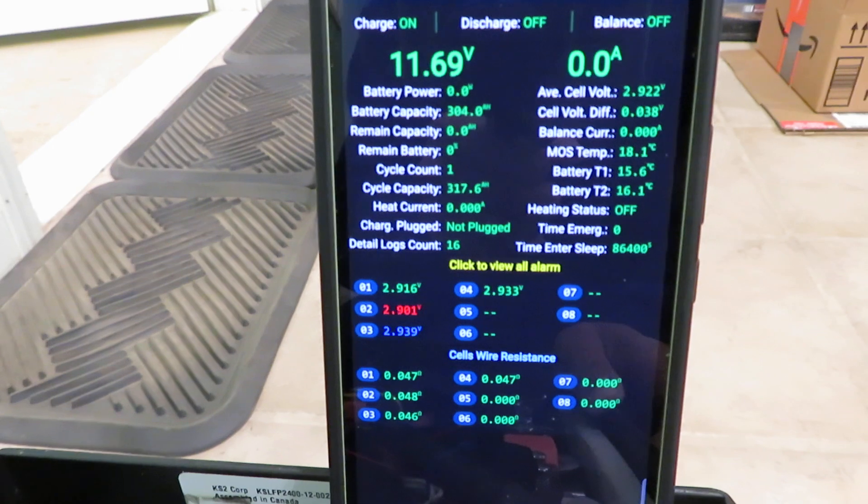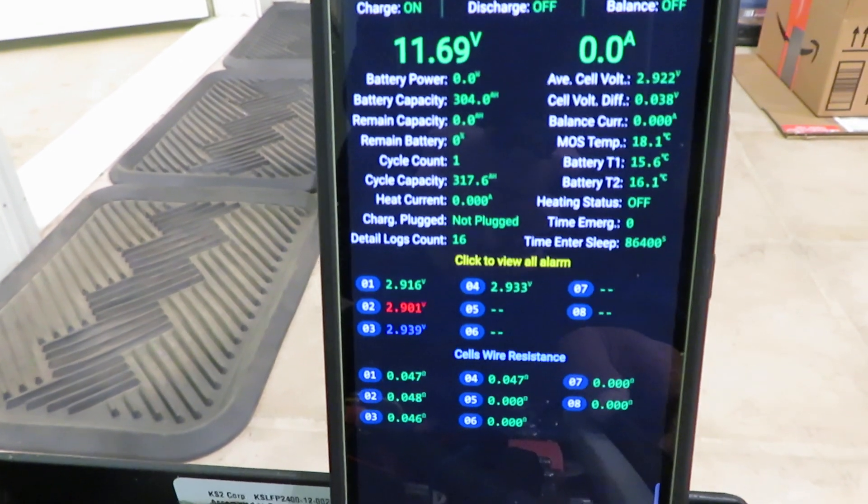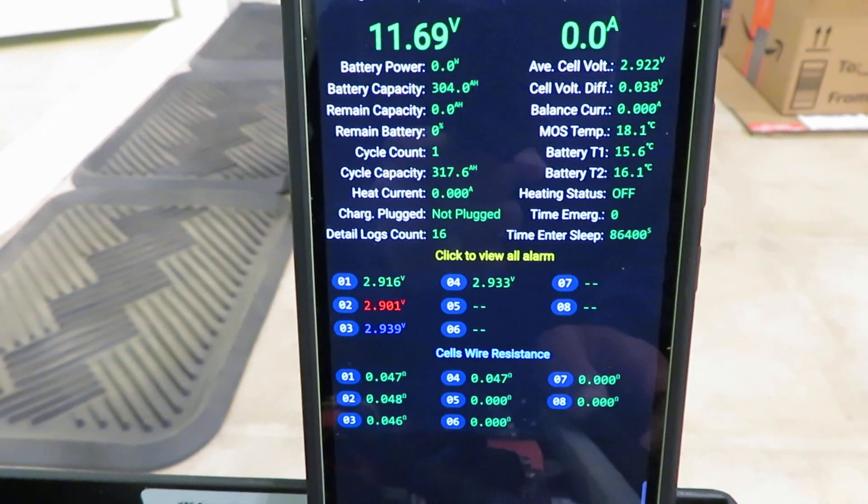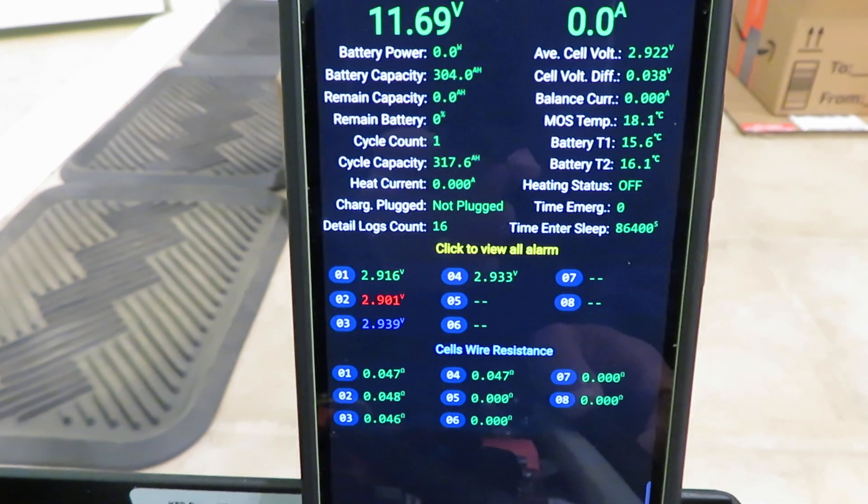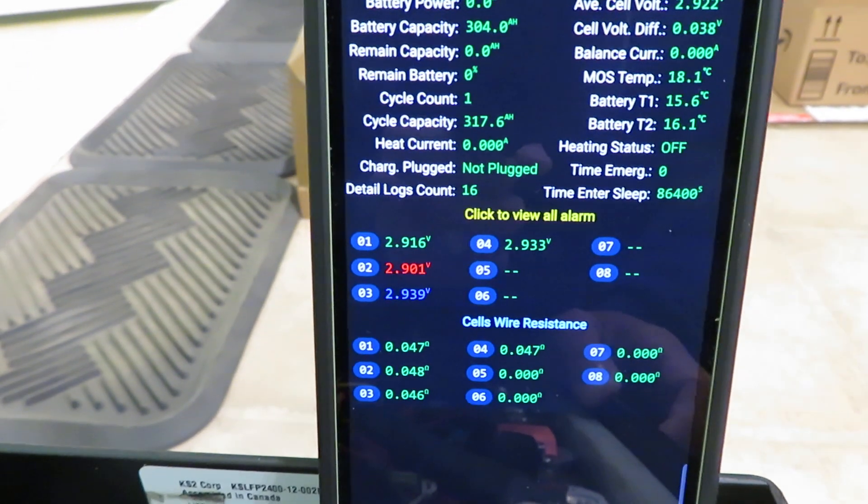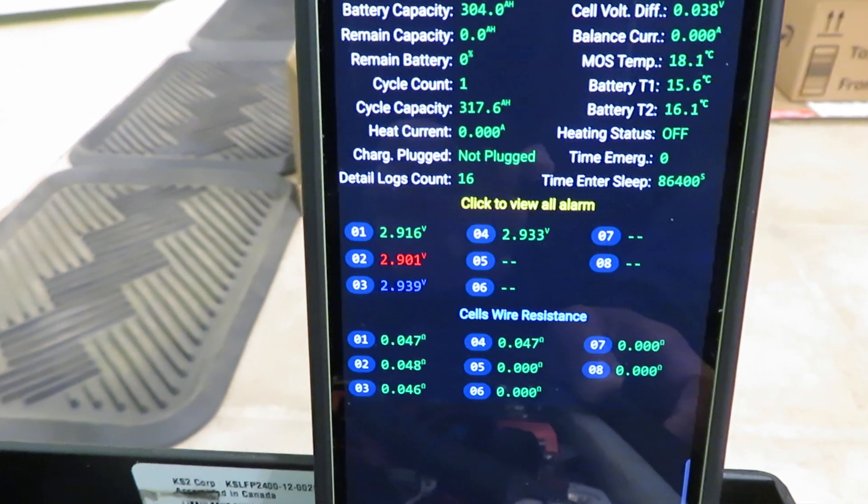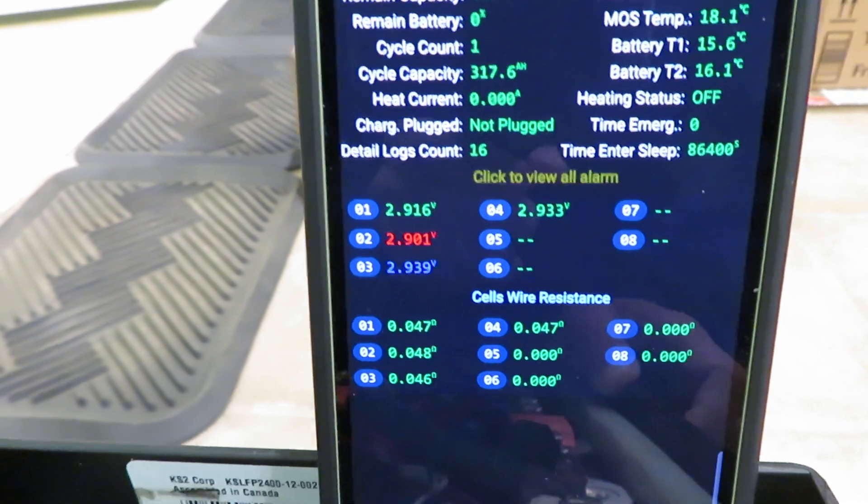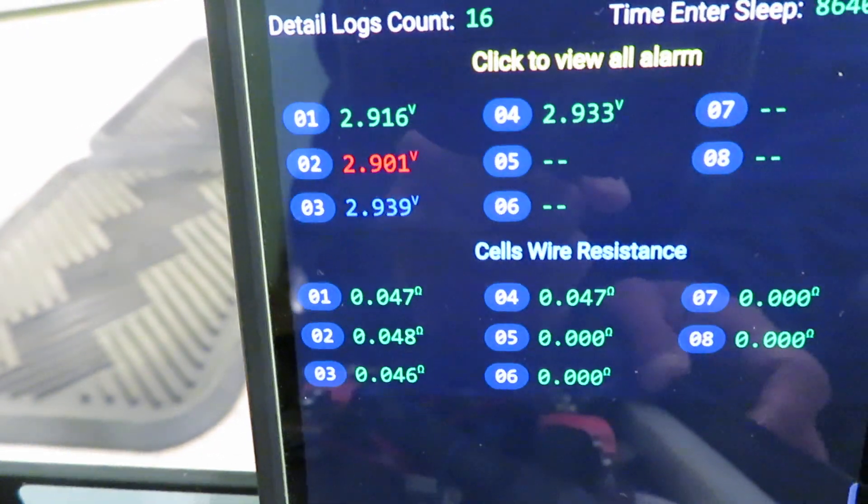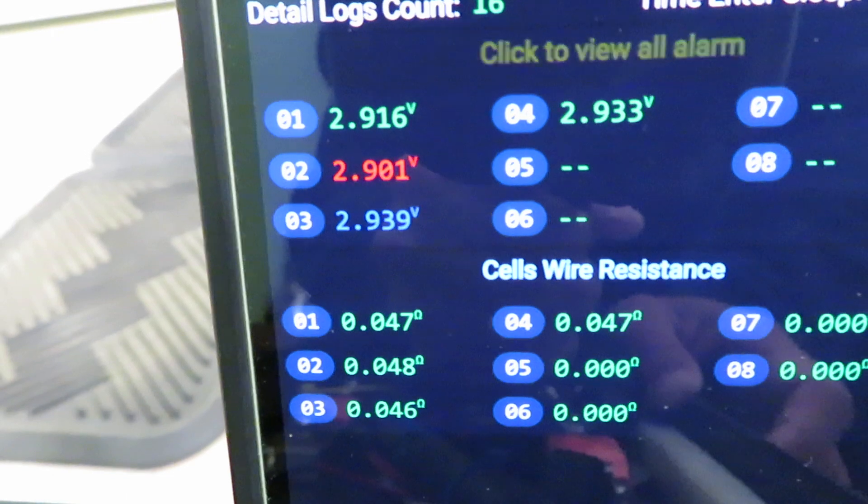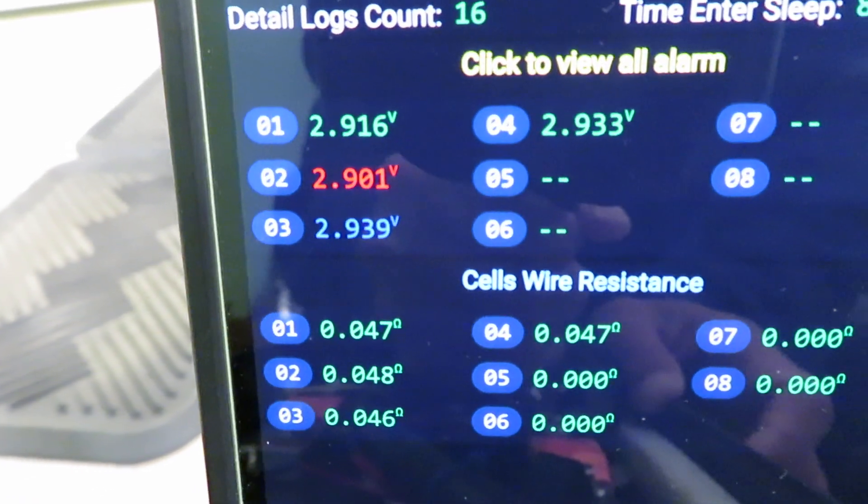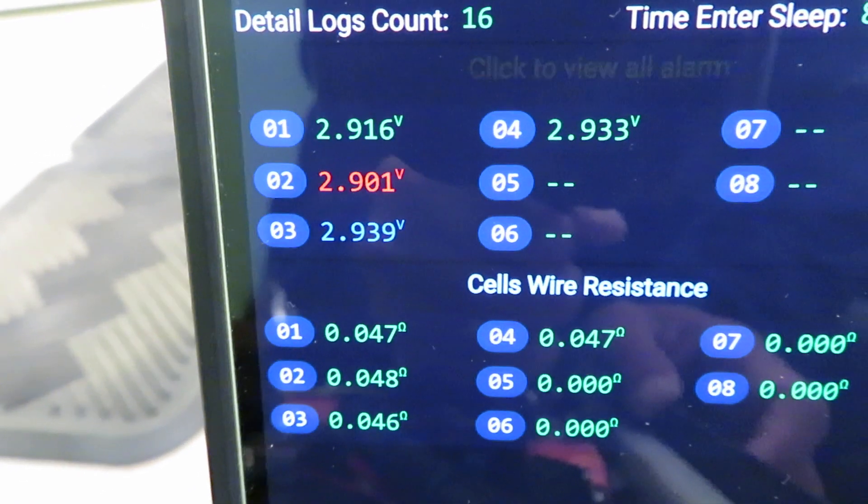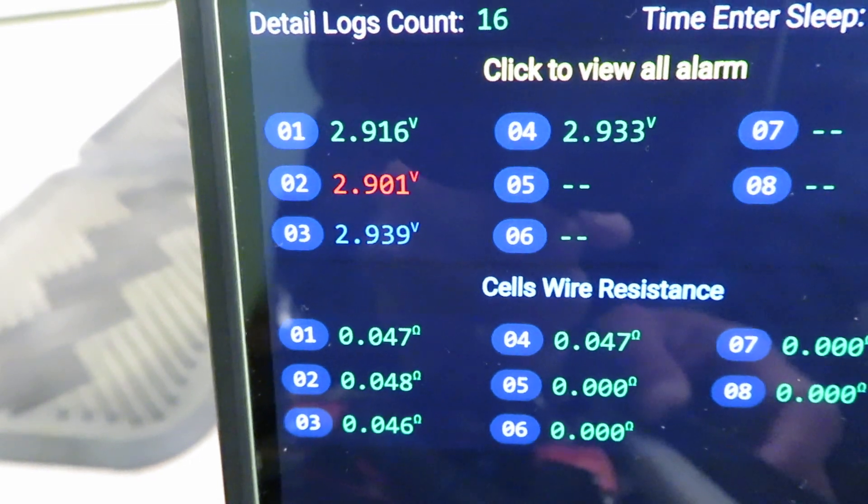The BMS controller was programmed to shut down at cell voltages lower than 2.85 volts. So it shut down a few hours earlier and now the cell voltages recovered back to about 2.9 volts.